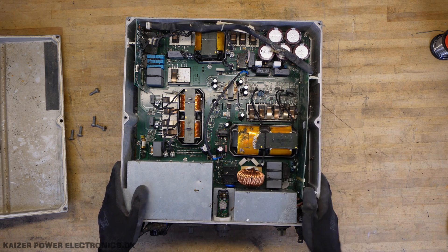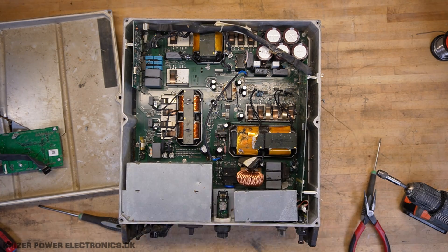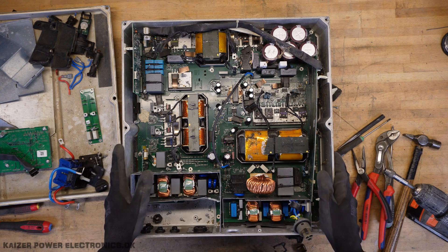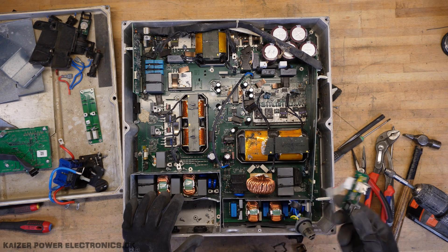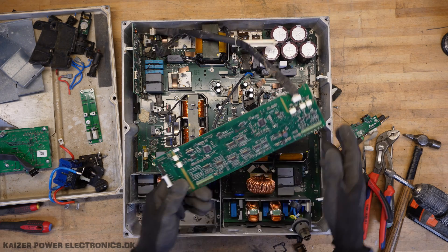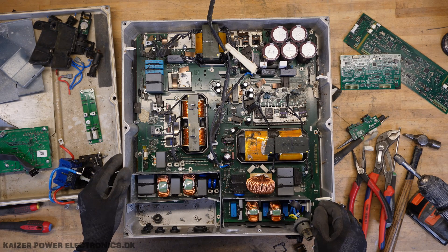As you can see, it really took a good smash at the junkyard — there are pieces of ferrite core everywhere. It's not exactly easy to service because a lot of screws are covered by components at the bottom, and especially this Modbus interface was really hard to get out without breaking it. This card connects to the Modbus. We have a single small microchip controller sitting there — let's take a look at that afterwards. We have another control board over here, which is most likely the inverter controller. Seems like a single controller board.